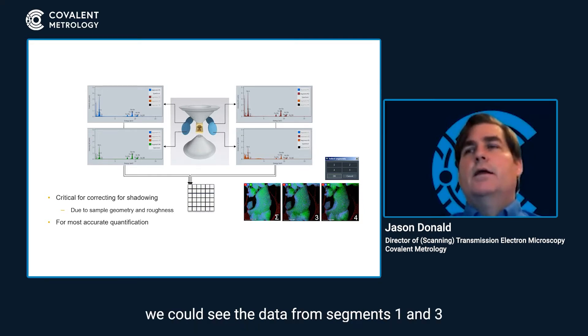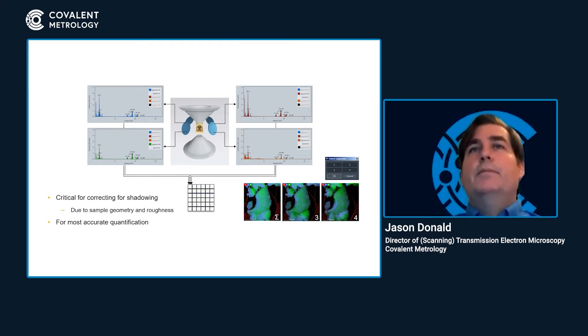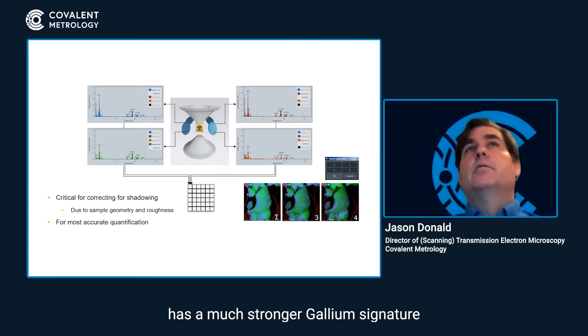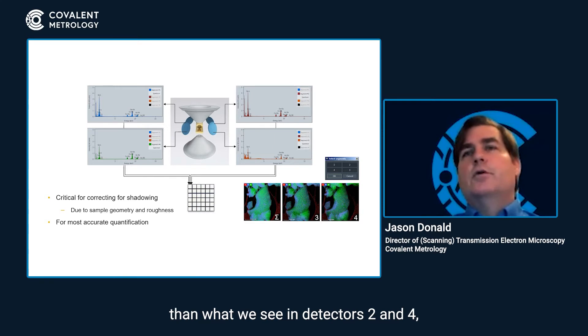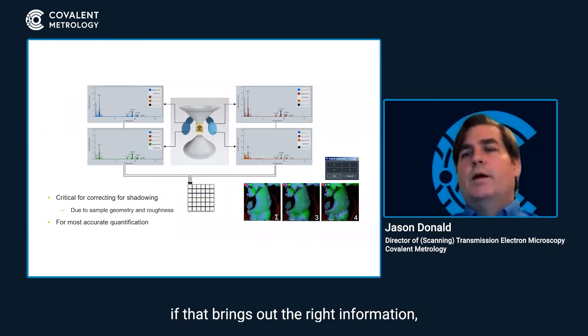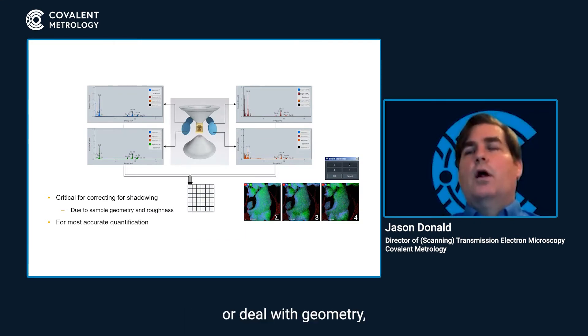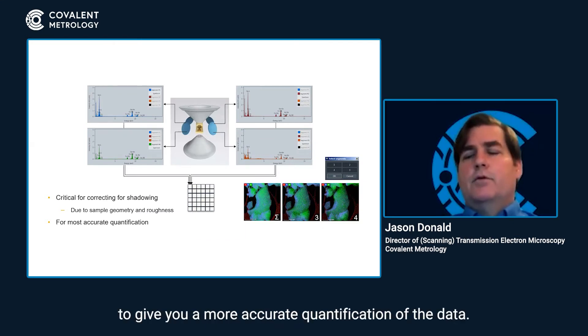we can see the data from segments one and three has a much stronger gallium signature than what we see in detectors two and four. And we can use that to shade the image if that brings out the right information, or deal with geometry that may be from the structure to give you a more accurate quantification of the data.